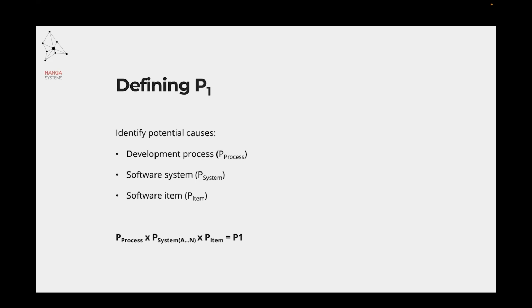Software risk control measures will help us to reduce the probability of failure, even though it is hard to estimate the level of reduction. First, we will have to identify the potential causes, and for this, we can break up P1 into three different areas. Development process, represented by P process. In an IEC 62304 class B or class C based development process, it's already going to be a kind of risk control measure because it is a requirement for us to document the development process applied for our device development.